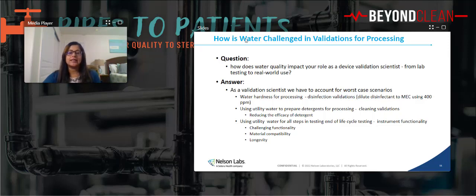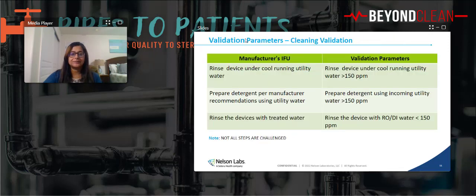Now, using utility water for all steps in testing—end-of-life use testing, big thing we're talking about right now. We use utility water throughout the whole process, just to make sure we know at what point the device will be non-functionable and break down. So manufacturers have an idea that if they use the worst water quality system, how long can my devices last? There's a lot of work being done on the validation testing lab side and manufacturers together to ensure that if something does go wrong and if there's no quality systems, if the water is not there, are our devices going to sustain, and is it going to be safe to process and use that device on a patient? So on our end, we take that into consideration.